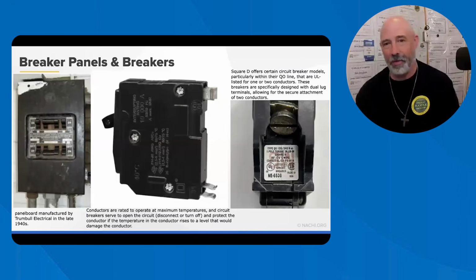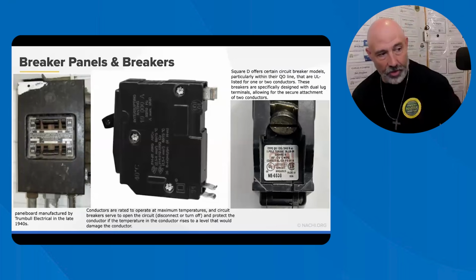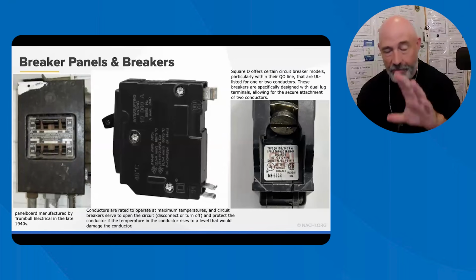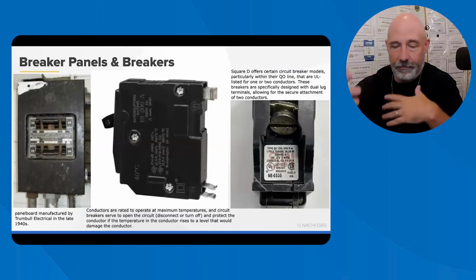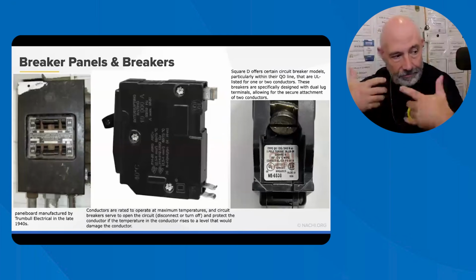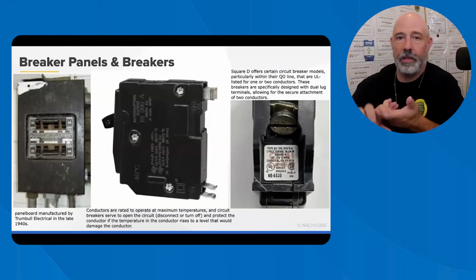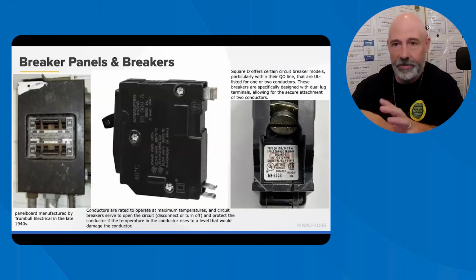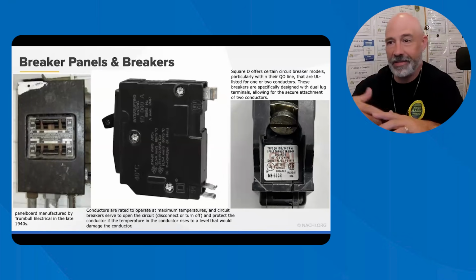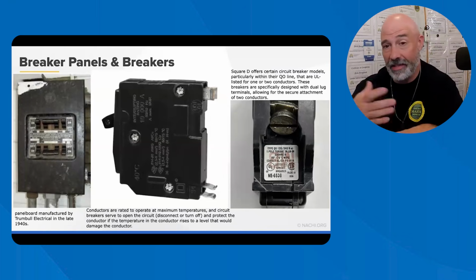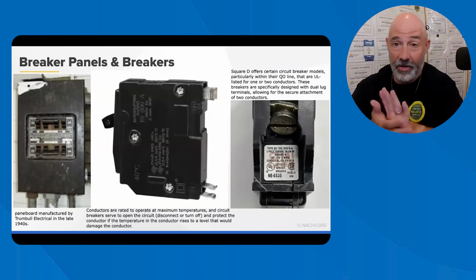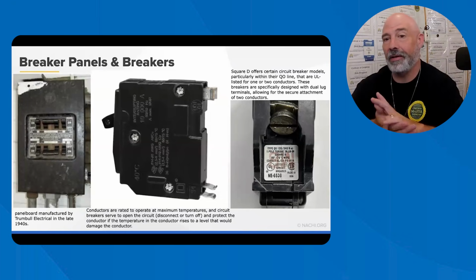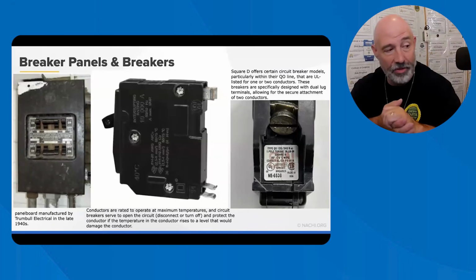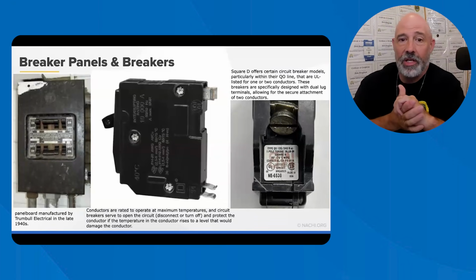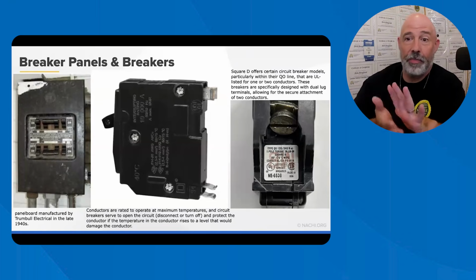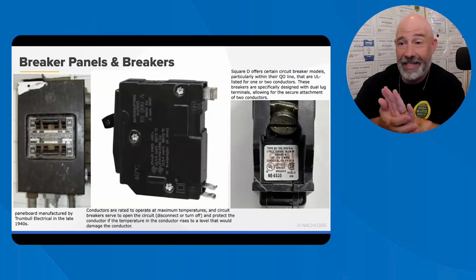Circuit breaker panel boards look similar. They do a similar job, but they're mostly feeding the house. That's their job. So these are probably the most common types that the home inspector should come across, and they have replaced fuse panels since the 1950s. In my opinion, fuses are awesome, but people have not used them correctly or put the wrong size in there. So breaker panels go further back than people actually realize. They actually were patented in 1910.